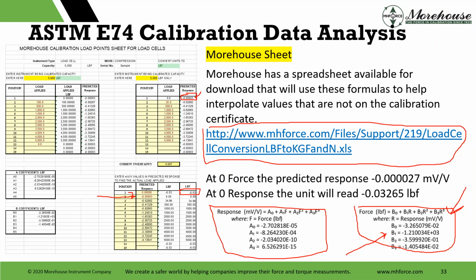So what happens when we put in negative 0.0003? We read 0. So that is the exact same as up here. At negative 0.0003, we expect, if we use this equation, to read 0. And then what essentially happens is this formula, this B coefficient, works from the calibrated force values. So if we start calibrating at 100 pounds, it will work from 100 pounds. You may have a negative 0.03 offset. That's how the math works, right? It is just how it works. This is where it starts.